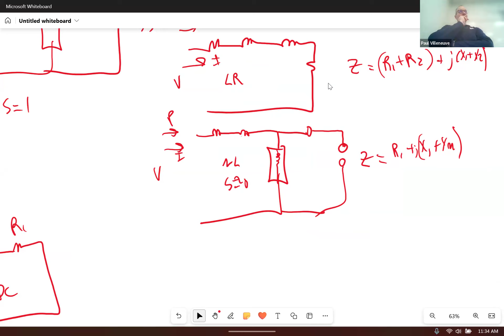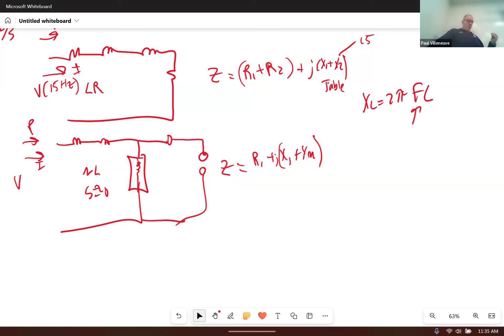But keep in mind, when you're doing the locked rotor test, that's working the motor really hard. So normally we run this at, let's say, 15 hertz. We run it at a much lower frequency so that we don't pull as much current, because the synchronous speed is really high at that point. So we're pulling in a lot of current. If this is only operating at 15 hertz, these X values are at 15 hertz as well, because it's 2 pi F times L, right? So if you run that at 60 hertz, you have to multiply those values by 4, because we're looking for the equivalent circuit at 60 hertz and not 15 hertz.